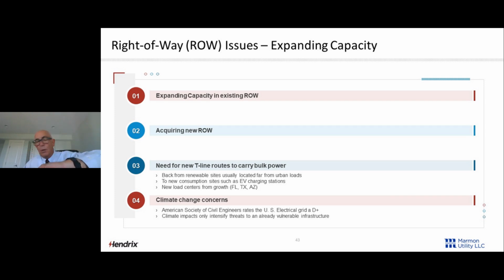So let's talk a little bit about the main issues. We talk about optimizing right of way. What do we want to do? We want to expand capacity. So the issues are we want to either expand capacity in an existing right of way or acquire a new right of way, because we need new transmission lines to carry bulk power. We're getting power back from renewable sites. We've got solar ranches out in the desert. We've got wind farms up on mountain ridges located far from urban loads. We've got to get that power back to where it's being consumed.